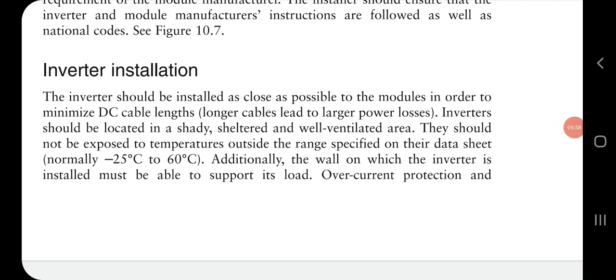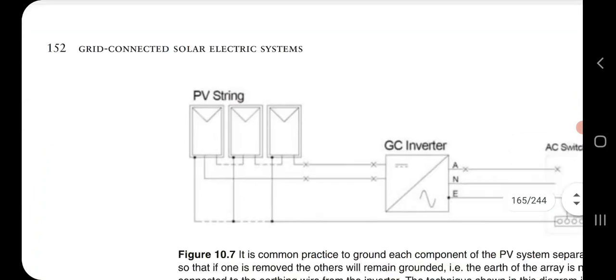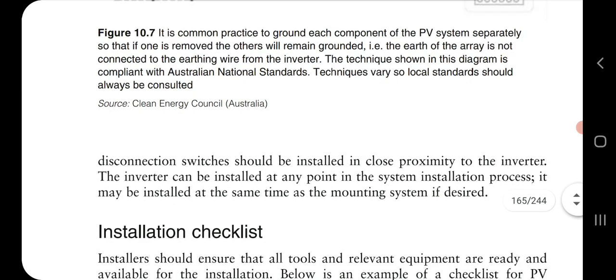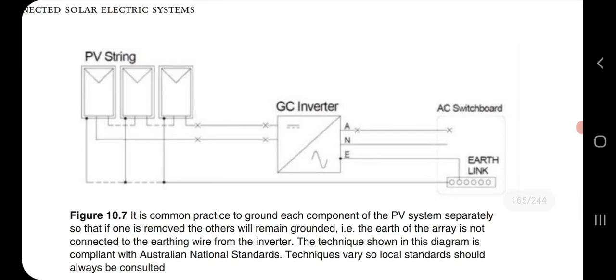Inverter installation. The inverter should be installed very near to the module. The reason is that if you install it near the module, the length of the wire gets reduced, and hence the power loss will also be reduced. It should be installed in a good place with shelter and a ventilated area. It should not be exposed to high temperature, and it should be easily accessible. Overcurrent protection and disconnection switches should be installed very close to it. And you can see this is the PV string, which goes to the inverter and then to the AC switchboard.